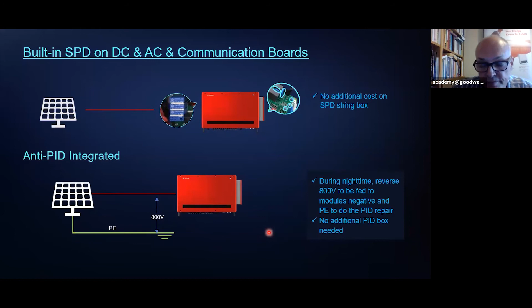Now, below here, we have a feature which can be added into the product, which is the anti-PID. So if panels are suffering from this during the daytime, then to reverse that problem, we do have the ability to generate a reverse voltage back across the solar panel to repair that. And we can do that because these inverters will power up from AC alone at night. You don't require the PV at night, so we can power these up and generate this 800 volt reverse polarity and repair any PID problems. So of course, what that means is you now don't have to go to the additional expense, cost and time of adding in this external box, this external function.